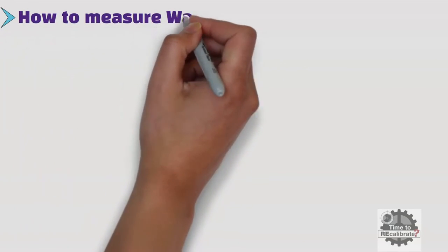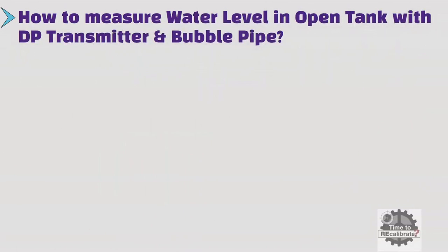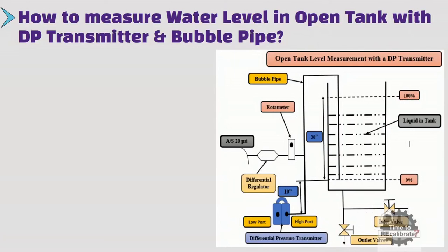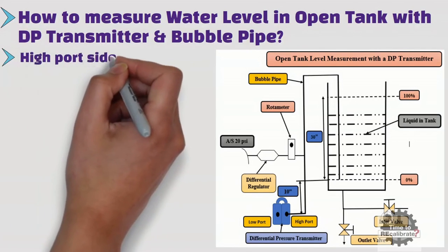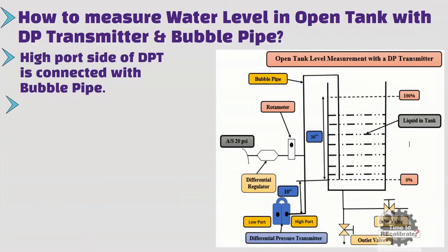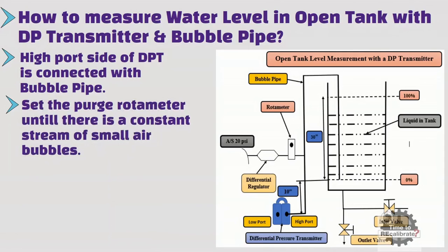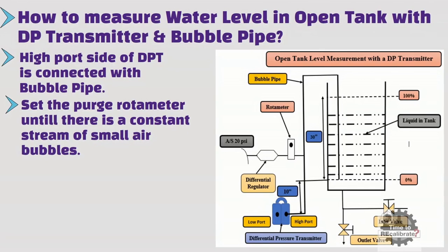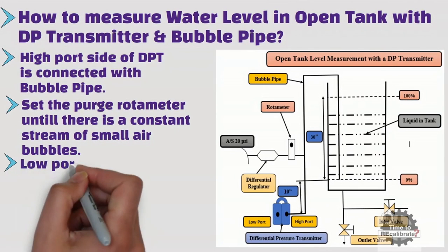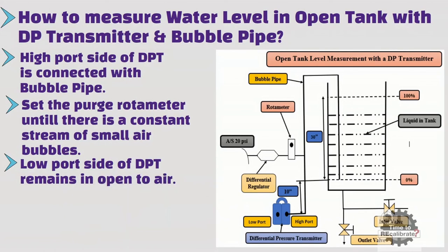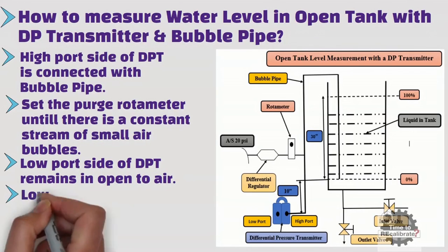How to measure water level in an open tank with a differential pressure transmitter and bubble pipe? As you can see from the picture, the differential pressure transmitter is installed 10 inches below the minimum level of liquid in the tank, and the high port side of the DPT is connected with the bubble pipe. Set the purge rotameter until there is a constant stream of small air bubbles. Because of the bubble pipe, the transmitter position does not affect the calibration range, and we can neglect the transmitter installation height. The low port side of the DPT remains open to air, so it has 0 inches H2O pressure.